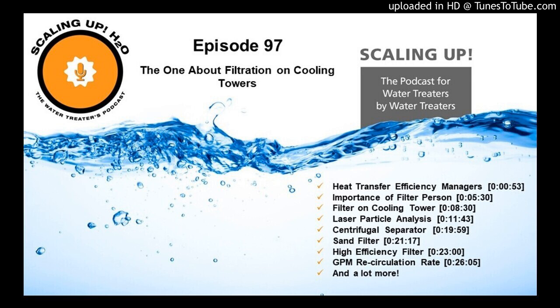But what happened is the first year after they put the sand filter in, they went into the sump to clean it, and they squeegeed it. No heavy sludge at all. They absolutely love the filtration system. So if you have heavy particle sump loading, it will significantly reduce that. I wouldn't make promises to my customers, but I would say, yeah, you're going to have a much cleaner sump, and let's see how it goes. But the reason for buying a sand filter is not so you can clean the sump less frequently. That's a nice thing, but that's just some maintenance expense.